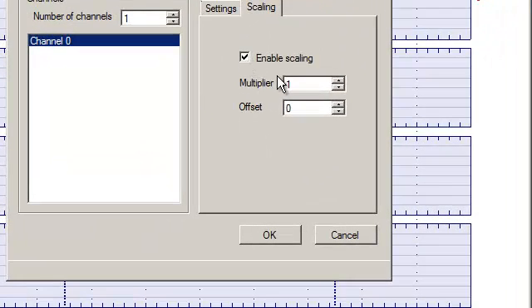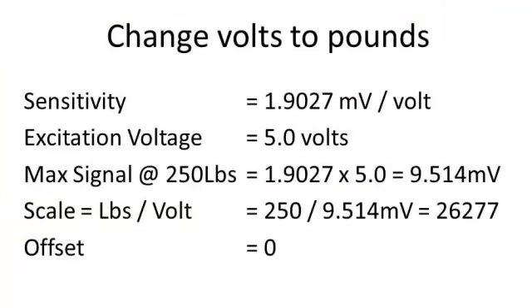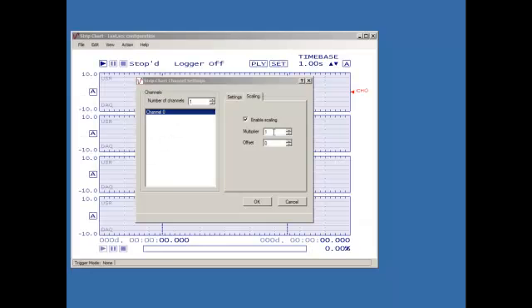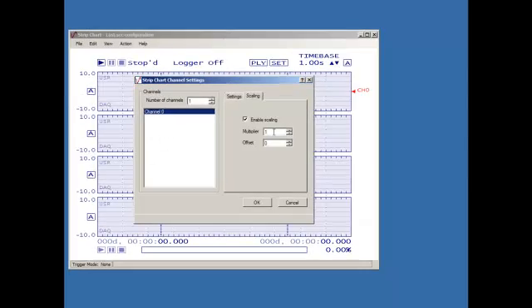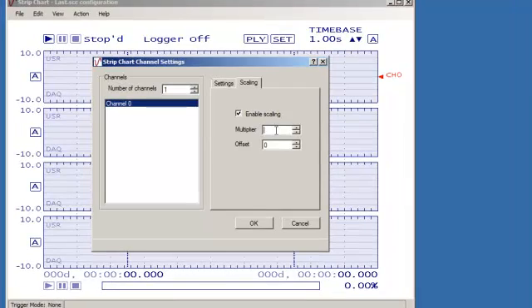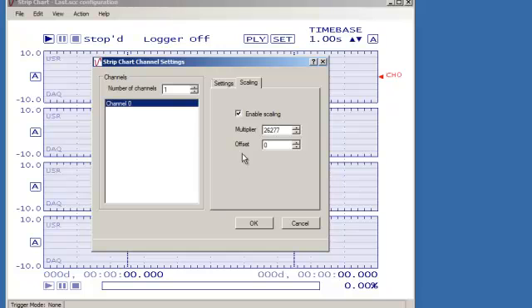Here, check the Enable Scaling option. Now I need to scale the output signal to pounds. To do this, take the sensitivity number and multiply it by the amount of excitation. I'm using 5 volts, so the maximum signal is 9.514 millivolts. Next, divide the maximum load by the maximum signal. This yields a scaling factor of 26277 pounds per volt. Or looking at it another way, it's 38.1 microvolts per pound. Enter 26277 in the multiplier box.